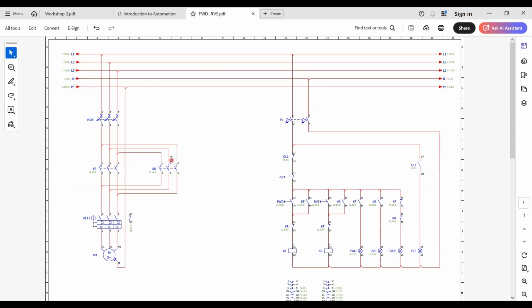So this is the basic power wiring, but we have to control these contactors using a control circuit. In our previous workshop, you studied 24-volt contactors, but now all the contactors operate using a 230 volts direct supply. So you need to use one phase for that and the neutral. Here the L1 phase is used. It doesn't matter which phase you're using. Either you can connect it to L2 or L3, but here L1 and the neutral are used.